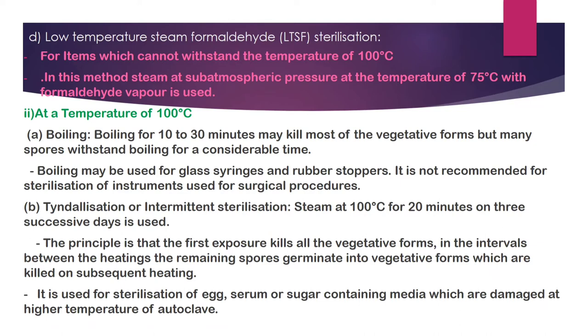At 100°C, boiling for 10 to 30 minutes kills all vegetative forms, but spores may withstand boiling for some time. Boiling can sterilize glass syringes or rubber stoppers, but it is not recommended for sterilization of instruments used for surgical procedures.